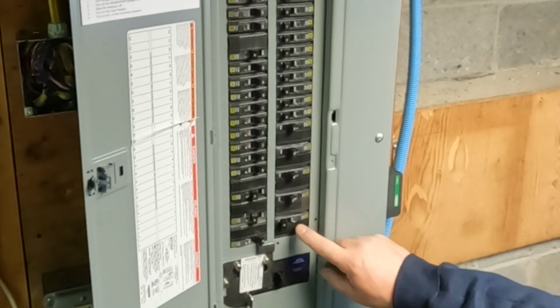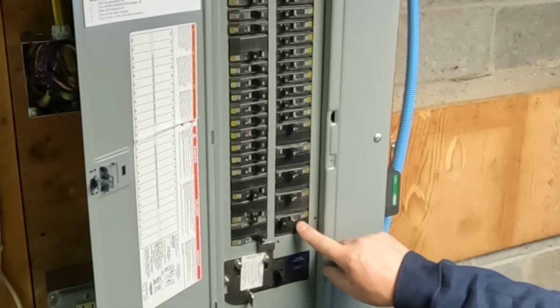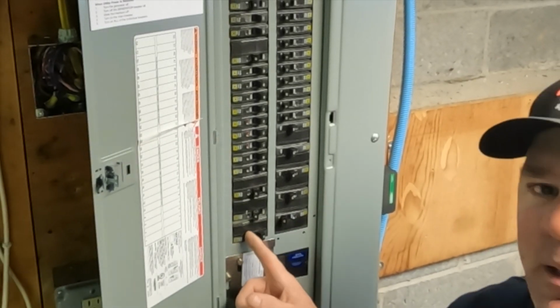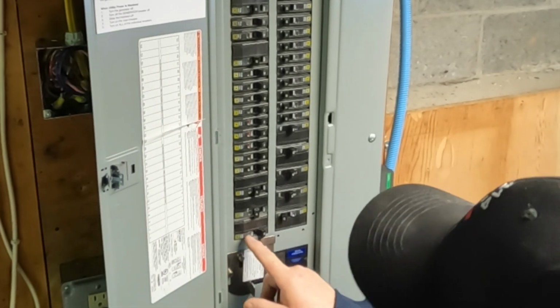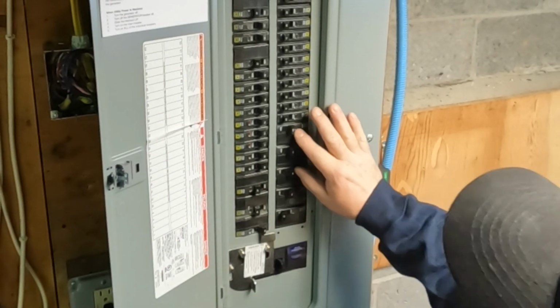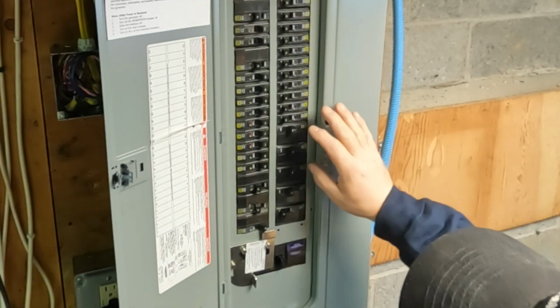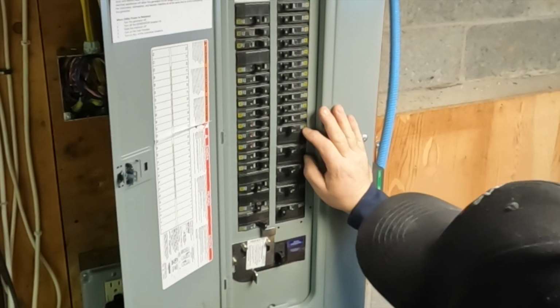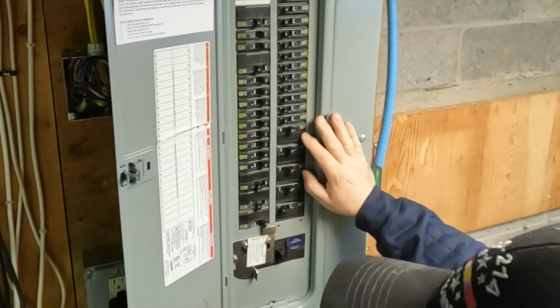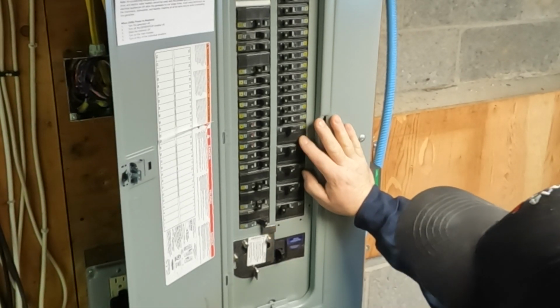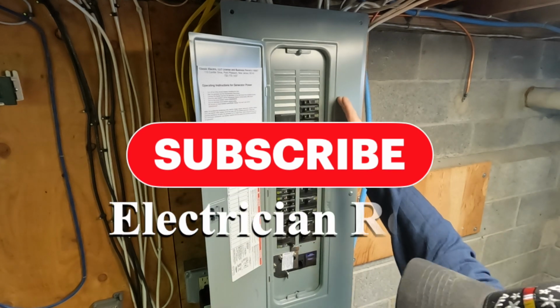As you can see now, the only double pole circuit breakers we have on are the surge protector and of course the interlock. This is back feeding the entire panel right here. These 40s, these 30s, and these other double pole circuits, one of them's for the pool, the other one's for the air handler. There's a condensing unit, a wall oven, that sort of thing. We won't be able to use that on the portable generator system, but we can do everything else, including our internet. That's pretty much it. As far as starting the generator up, that's really all we got to do. Make sure you stabilize the voltage by starting the generator up and let it run for about 5 minutes before you connect everything like we did.